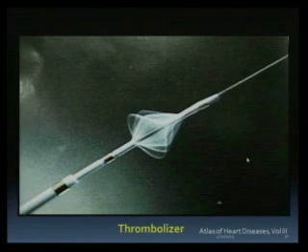This is a Thrombolizer. This is, I think, developed by Harvard University. I don't know if they have continued on with their experiment. This is a simple catheter with slits towards the end. If you subject it to several thousands of RPM, it would open like a basket. And as it opens the basket, it's softer than a wire, and therefore it will tend to break into the thrombus and at the same time suck the thrombus into the lumen of that particular catheter.